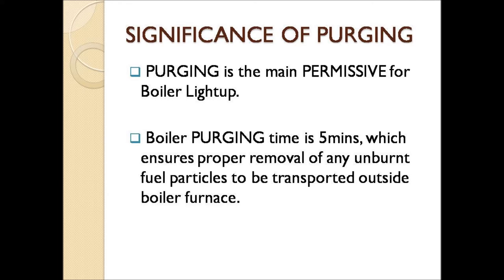Purging is the main permissive for boiler light up. If purging is not done, then there will be no permissive for boiler light up. Boiler purging time is set at 5 minutes. This is because it ensures proper removal of unburned fuel particles to be transported outside the boiler furnace.